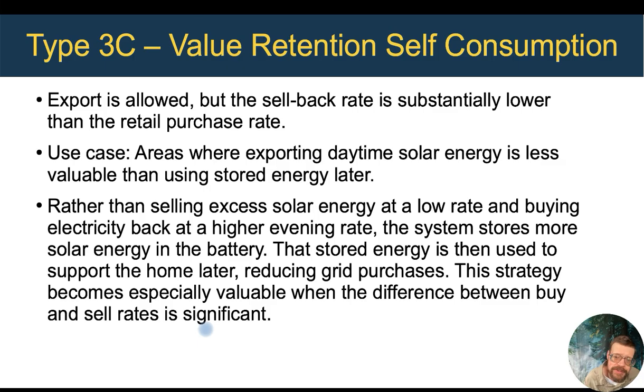So what we want to do is use the batteries as much as possible to power our own loads, and when the batteries are full, then we sell back, and maybe use some smart loads to do some opportunity dump loads if we can use it instead of selling back. Turn on the EV charging once the batteries get full, rather than selling back and charging the EV later from higher priced power. We want to make sure for any of these systems that we're using our batteries instead of the grid, that we consider the cost of operating the batteries.